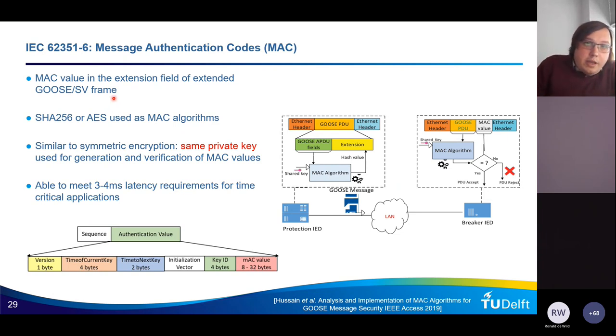So we can use message authentication codes to check the integrity of the GOOSE and sampled values packets or data frames. Now we use encryption algorithms, so the Advanced Encryption Standard or Secure Hashing Algorithm can be used to generate the message authentication codes. This is similar to symmetric encryption, so the same private key is used for generation and verification of the message authentication code values. And I will explain how it works in a second, but it's very important to note that this solution meets the real-time requirements for critical applications. Because if we want to encrypt, of course, we add an overhead, but this solution is actually very efficient.